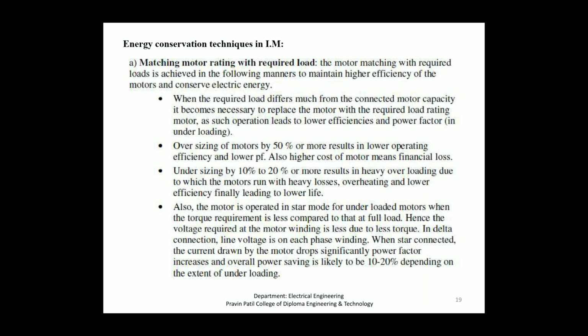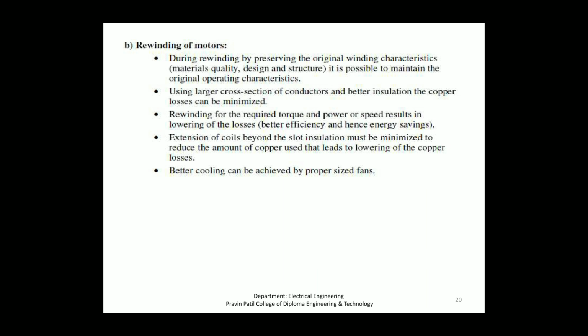The efficiency of a motor operating at loads below 40% is likely to be poor, and energy savings are possible by replacing these with properly sized motors, new or interchanged with another load. An incorrect selection of motor always leads to various problems such as premature failure of the motor, causing severe production loss. Next one, the rewinding of motors.